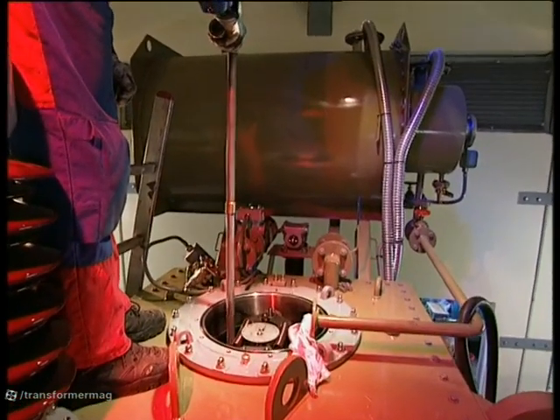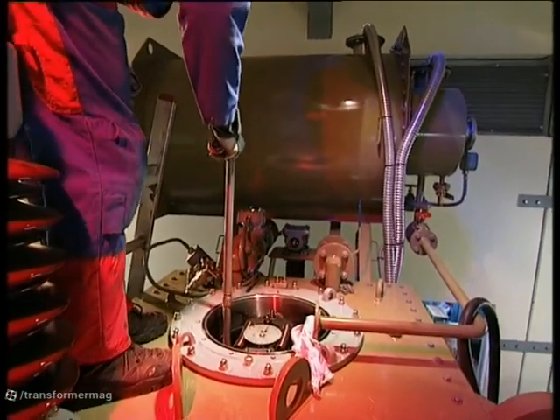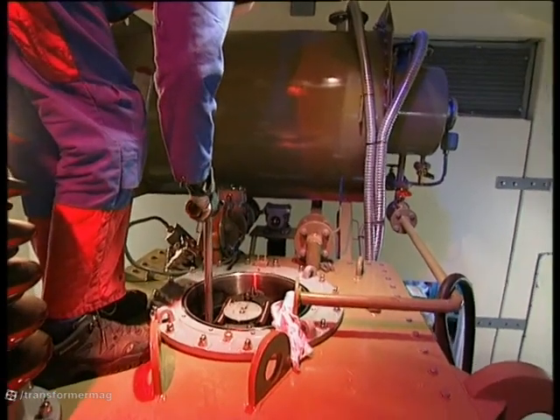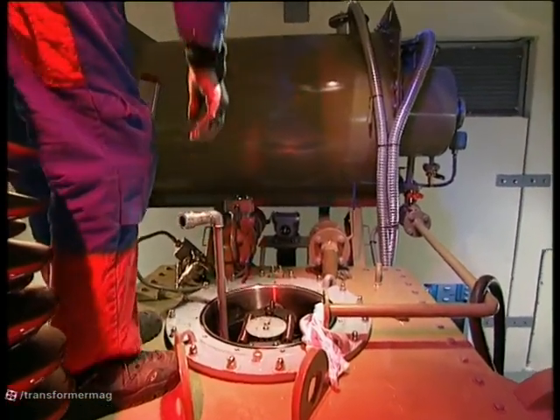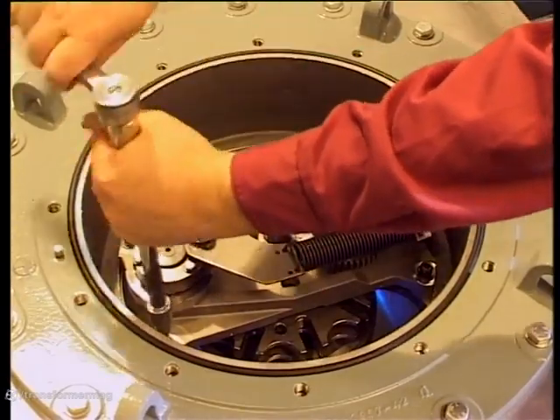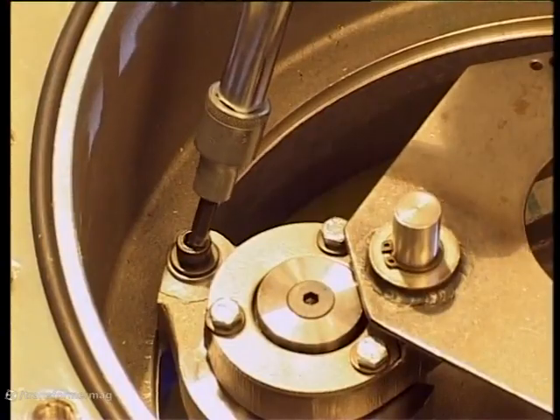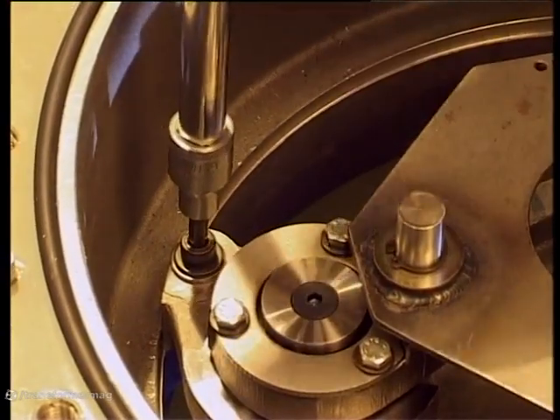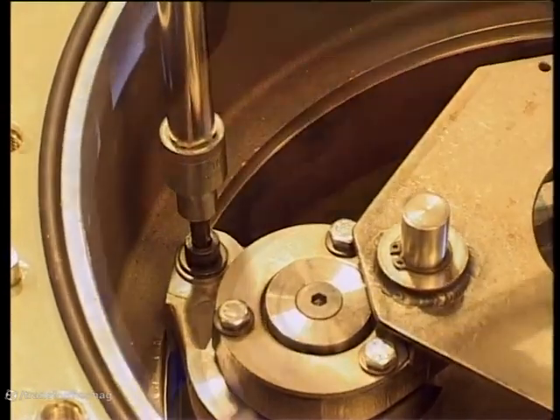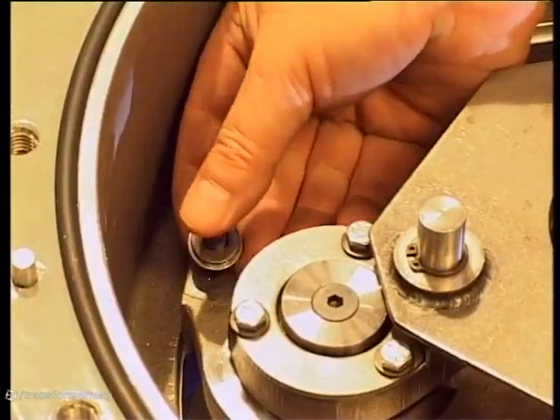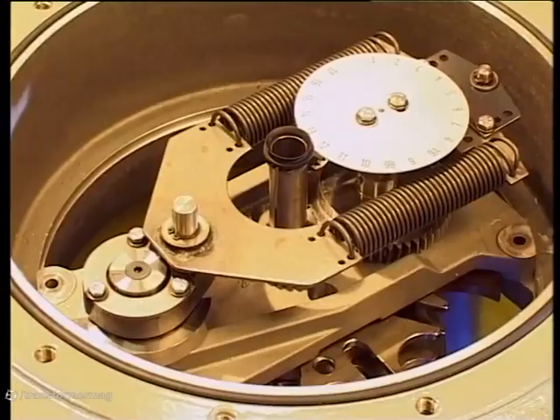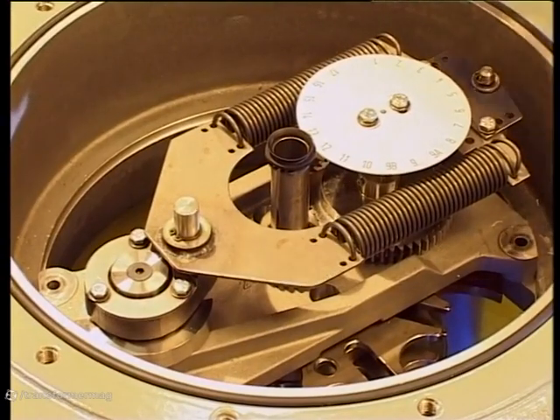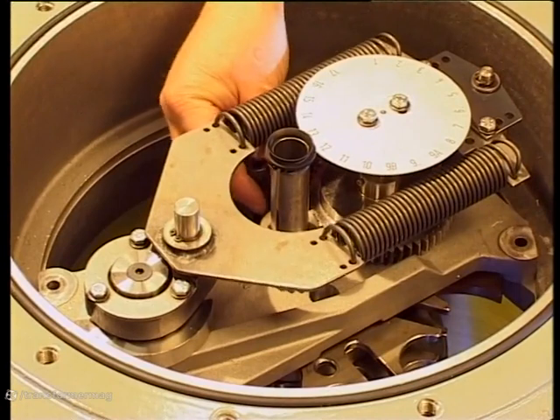You now drain the rest of the oil by passing the tube down to the bottom of the switch cylinder and drawing it off by suction. To remove the mechanism, slacken the 4 M8 Allen screws at the corners of the bearing plate. If the plate is stuck in place, this is what you do.